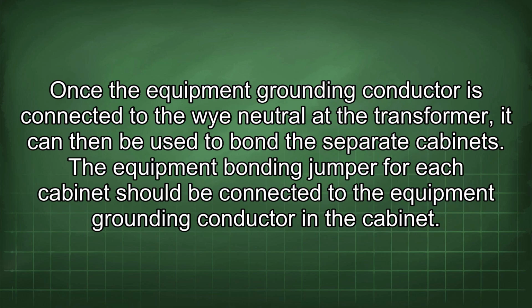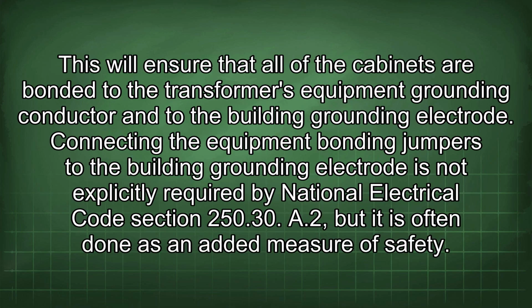Once the equipment grounding conductor is connected to the Y neutral at the transformer, it can then be used to bond the separate cabinets. The equipment bonding jumper for each cabinet should be connected to the equipment grounding conductor in the cabinet. This will ensure that all of the cabinets are bonded to the transformer's equipment grounding conductor and to the building grounding electrode.